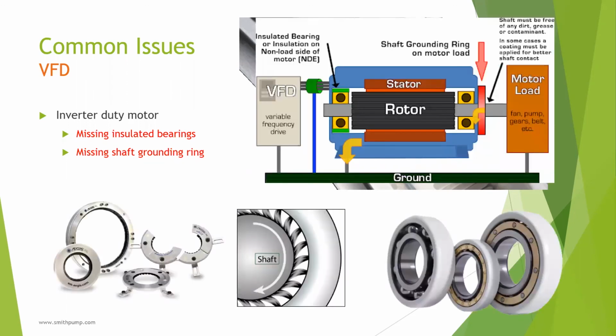We recommend 2 upgrades on a motor when using a VFD. The first are insulated bearings. A special coating on the bearing resists an easy electrical path for charged rotor. That charge is grounded by the use of a shaft grounding ring.